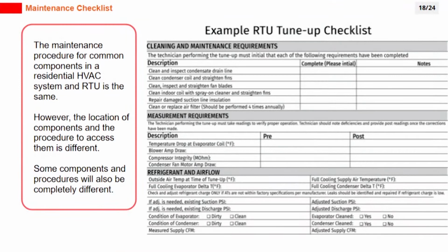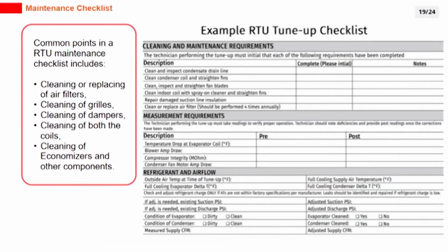Maintenance procedure for common components in a residential HVAC system and RTU is the same. However, the location of components and the procedure to access them is different. Some components and procedures will also be completely different. Common points in an RTU maintenance checklist include cleaning or replacing of air filters, cleaning of grills, cleaning of dampers, cleaning of both the coils, cleaning of economizers and other components.